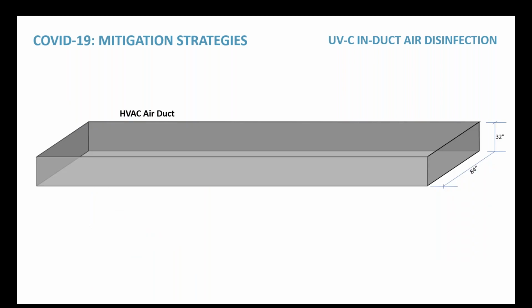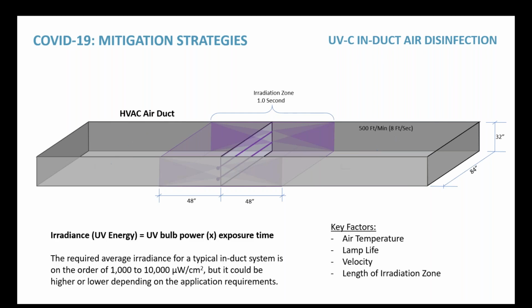It's very important to understand that all of the technologies that we're talking about, especially with UV, are not necessarily one-size-fits-all. There's a lot of criteria that goes into defining how effective these are going to be. So here's an example of a UV system that is placed into a duct. You have to make assumptions about what the velocity is, in this case 500 feet per minute. That might be a velocity that you would find at an air handling unit. However, in some duct systems, you may have velocities that are much, much higher than that. And so then you have to start looking at the irradiation zone, right?